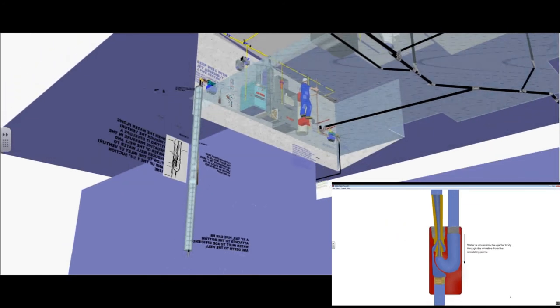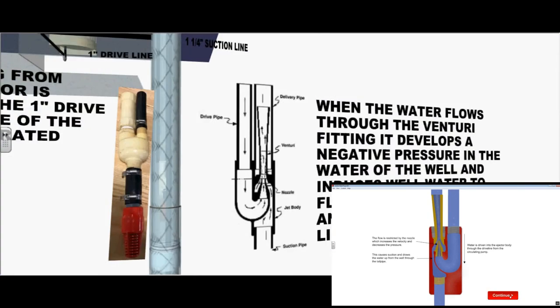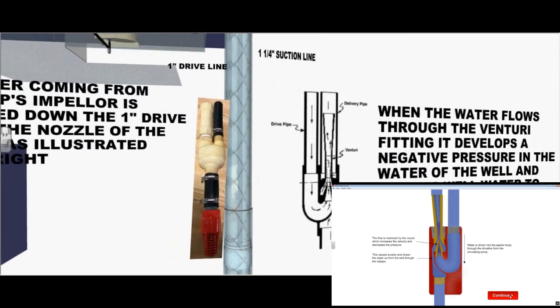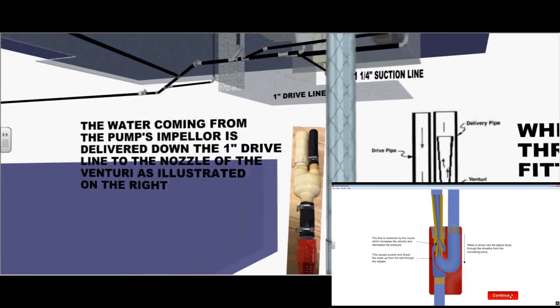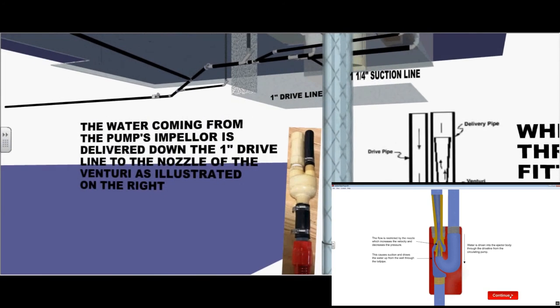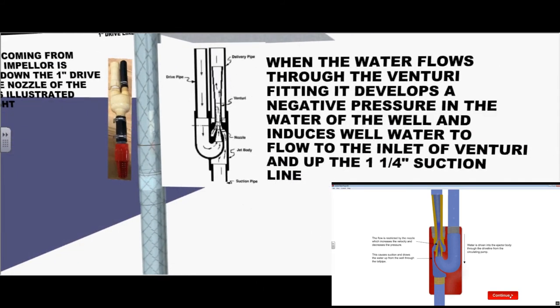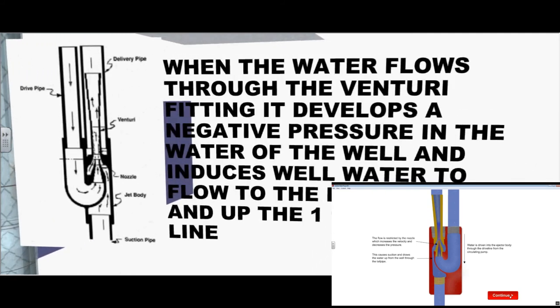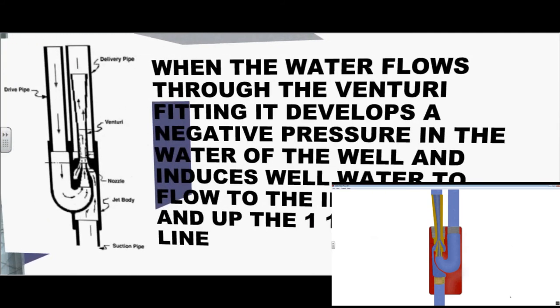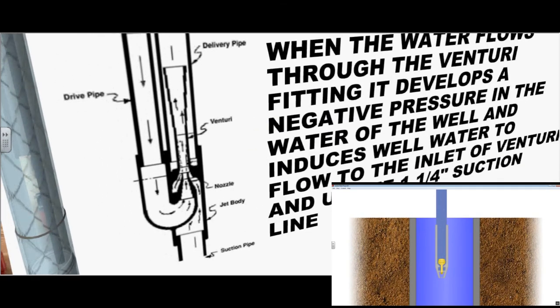Let's go further down the well and rotate around. We'll take a look at the jet assembly. The water coming from the pump's impeller is delivered down the one inch drive line to the nozzle of the venturi. When the water flows through the venturi fitting, it develops a negative pressure in the water of the well and induces well water to flow to the inlet of the venturi and up the inch and quarter suction pipe.